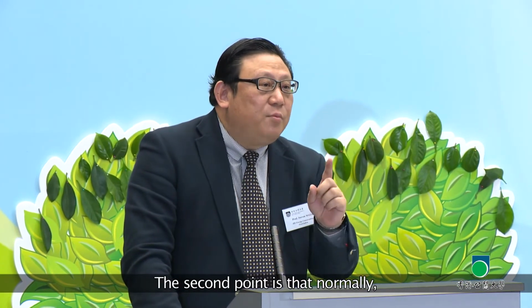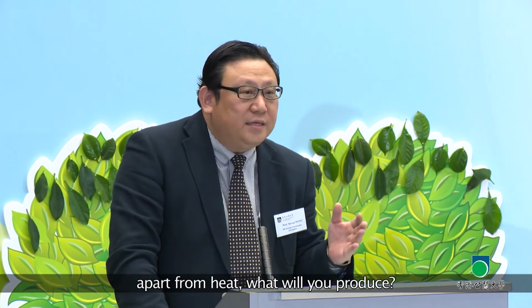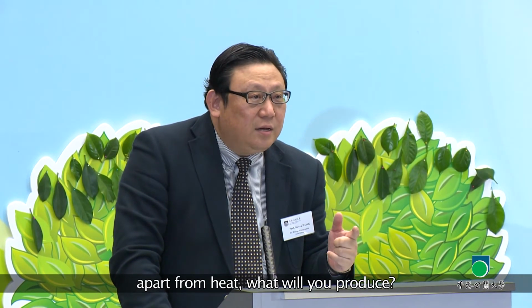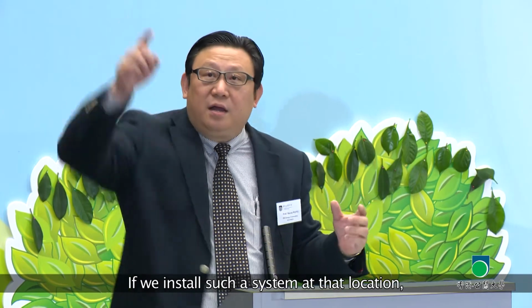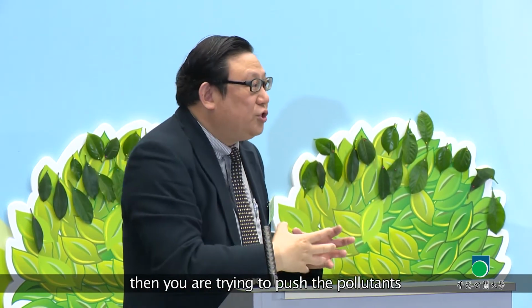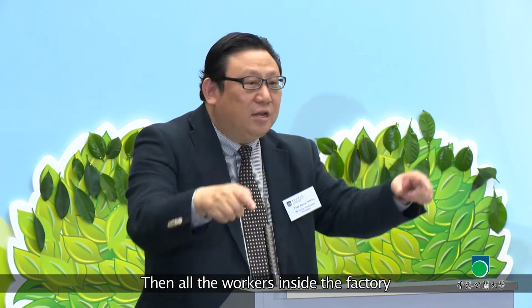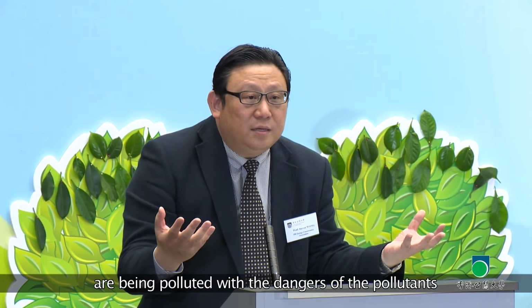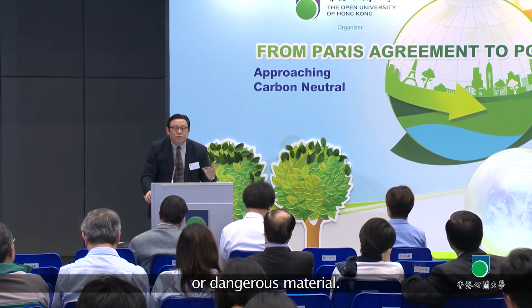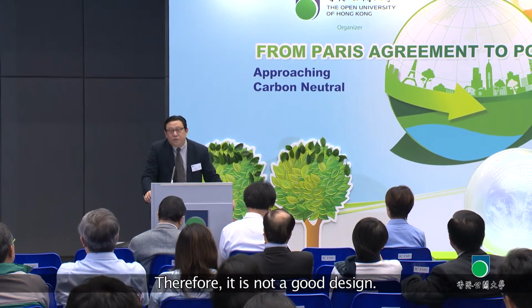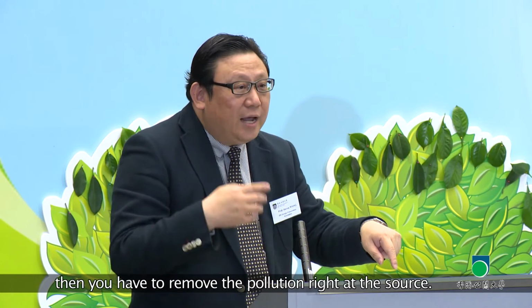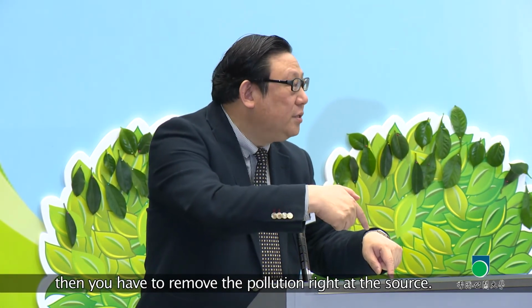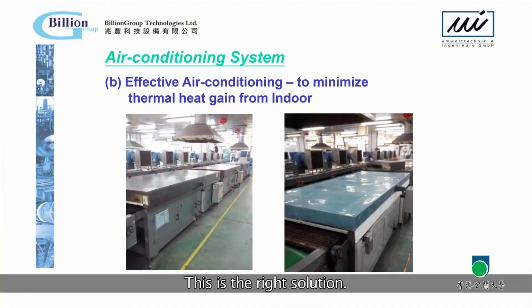The second point is that during manufacturing processes, apart from heat, you also produce pollutants, VOCs, am I correct? If you install such a ventilation system away from the source, you push the pollutants all around the factory, and all the workers inside get exposed to these dangerous materials. So it's not a good design. The best design is that when pollution is created at the source, you remove it right at the source - that is the correct solution.